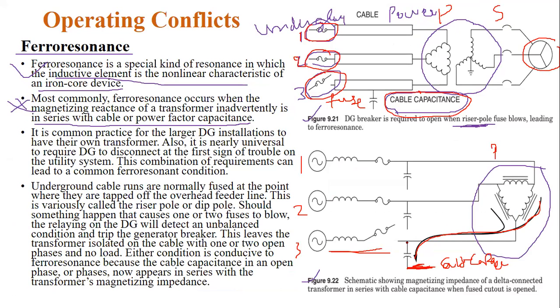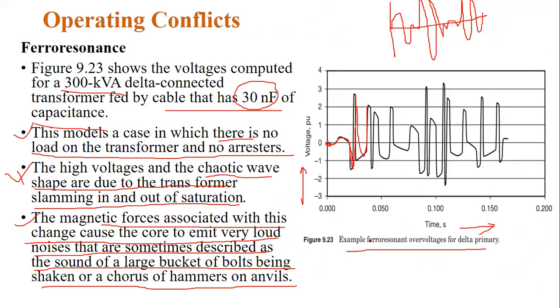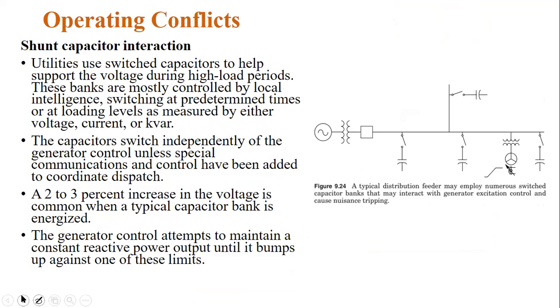If any one of the fuses is blown or any one of the circuit breakers is open, then on the delta side, the primary side of the transformer, one phase out of the three phases is connected directly to the cable capacitance when the fuse is blown. That may lead to a resonance problem, and because of that resonance the transformer gives some loud noise. It may still continue and maybe damage the core of the transformer, but the inductive element of the transformer. So this is one of the operating conflicts while we are connecting these DGs to the system. Then what is another conflict here, the most important conflict: the shunt capacitor interaction.